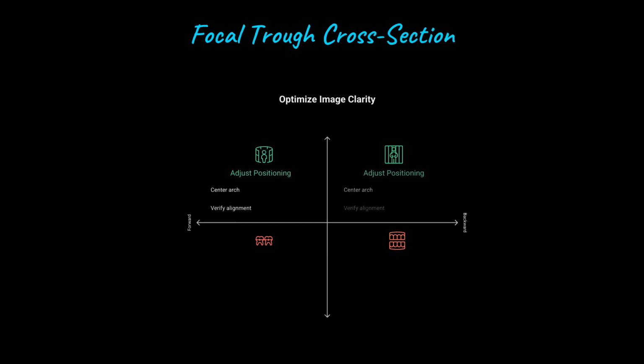Panoramic imaging sweeps a narrow beam around the head to capture the entire dental arch on one image. The key principle governing image quality is a concept called the focal trough, and understanding it explains why positioning is so critical in panoramic technique. The focal trough is a three-dimensional horseshoe-shaped zone that follows the curve of the jaws. The X-ray source and receptor rotate in coordinated motion, and only anatomy sitting within this curved band is recorded in step with the receptor's movement, producing a sharp image.